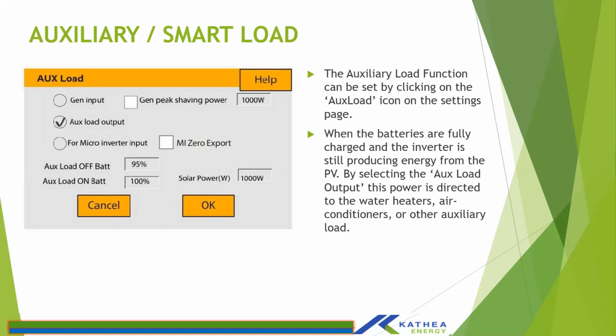So on aux load, you need to select aux load output to notify the inverter that you are using that port as a load output port. And then you set the cutoff for the port and the cut on. For instance, as per the image on screen, when the system battery gets to 100%, you can activate the port and supply solar power of 1,000 to this port, whether you are running a pump or heaters and all that. Once the battery drops to 95, it cuts out that port. So you can actually use this aux port as a smart load port as well.